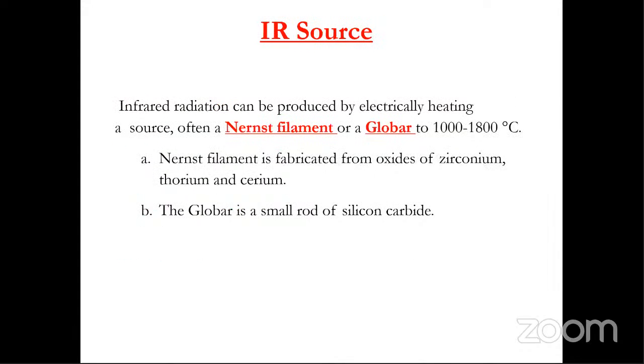So, types of sources: infrared radiation can be produced electrically by heating a source, often a Nernst filament or a globar, at 1,000 to 1800 Celsius. The Nernst filament is fabricated from oxides of zirconium, thorium, and cerium, and the globar is a small rod of silicon carbide.